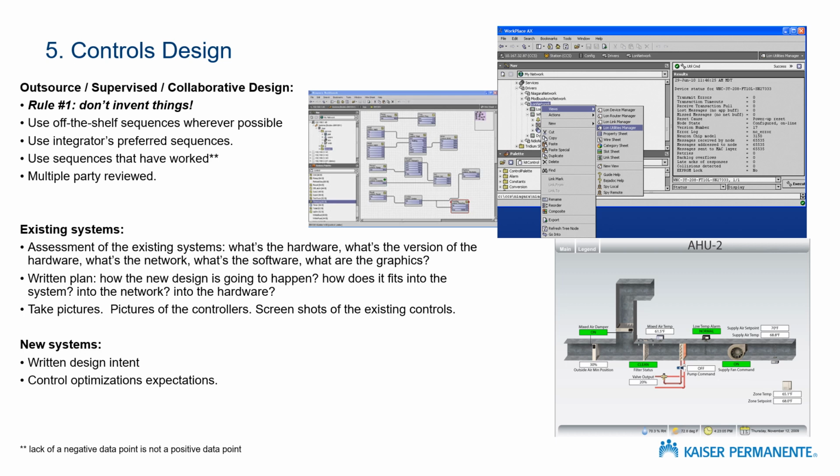I think we've learned the hard way. If there's a rooftop unit on the job or a factory chiller on the job, then we've got to have that vendor write their own sequences. And then we've had jobs where the controls integrator provides the sequence and the engineer supervises that. That works fine. We have jobs where the commissioning agent writes the sequence or supervises the writing of the sequence. That seems to work fine. But it's always got to be a multi-party effort. We have to maximize the use of specialists within the process of this design. And we really want to see that within the design process.